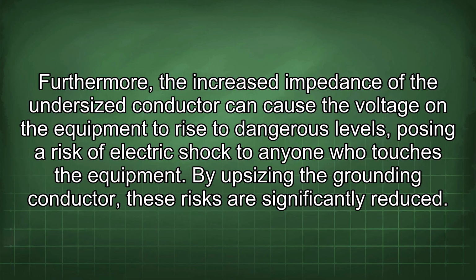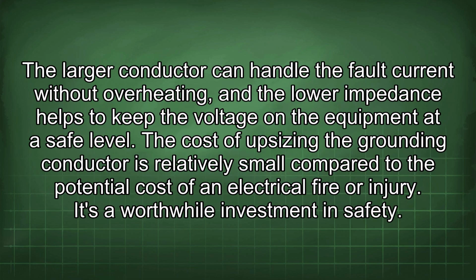By upsizing the grounding conductor, these risks are significantly reduced. The larger conductor can handle the fault current without overheating, and the lower impedance helps to keep the voltage on the equipment at a safe level. The cost of upsizing the grounding conductor is relatively small compared to the potential cost of an electrical fire or injury. It's a worthwhile investment in safety.